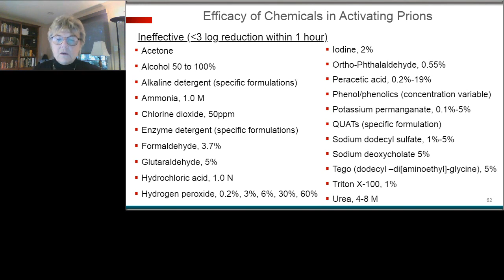Ineffective, they have found that acetone, alcohol 50 to 100%, alkaline detergents, ammonia, chlorine dioxide at 50 parts per million, enzyme detergents, formaldehyde at 3.7%, glutaraldehyde at 5%, hydrochloric acid at 1 normal, hydrogen peroxide at each of those up to 60%, not effective. Isn't that amazing? Also, all of these, iodine, peracetic acid, at those specific percentages were not effective.